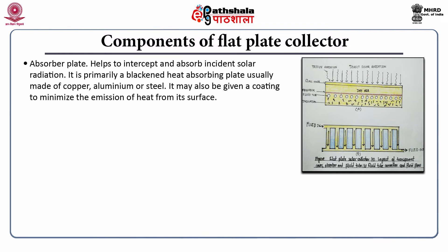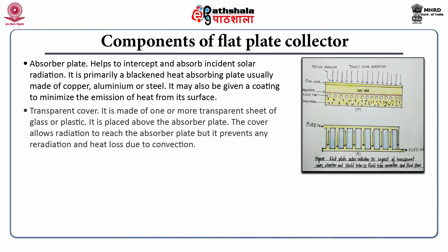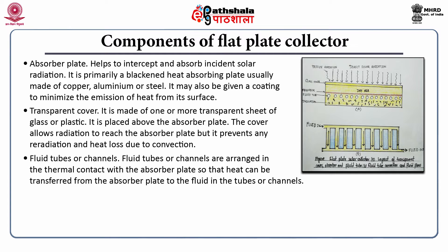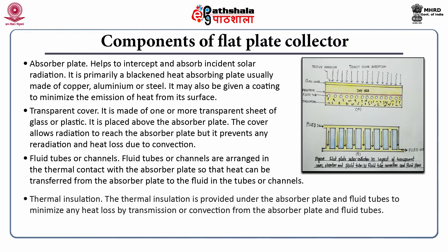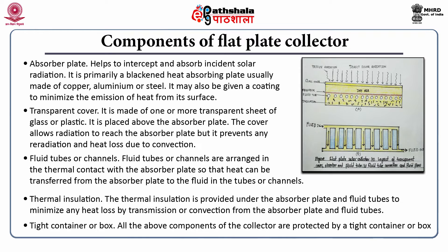The components of a flat plate collector include: the absorber plate, a blackened heat-absorbing plate usually made of copper, aluminum, or steel with a coating to minimize heat emission; the transparent cover of one or more sheets of glass or plastic placed above the absorber plate, which allows radiation to reach the absorber but prevents re-radiation and convective heat loss; fluid tubes or channels in thermal contact with the absorber plate for heat transfer; thermal insulation under the absorber plate to minimize heat loss; and a tight container or box protecting all components. The figures show the layout and fluid tube connections of a flat plate solar collector.